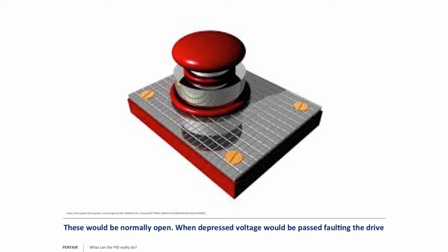Now, unlike the run command, if you program the faults here on the inputs, they will show as an external fault, and it will be a hard stop, meaning that because we do not know what you're programming, anytime there's an external fault, it's a hard stop. You have to reset the safety first and then hit fault reset and auto start in order to get the VFD running again.